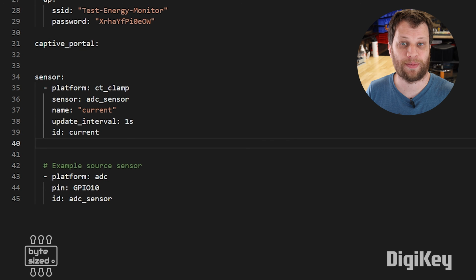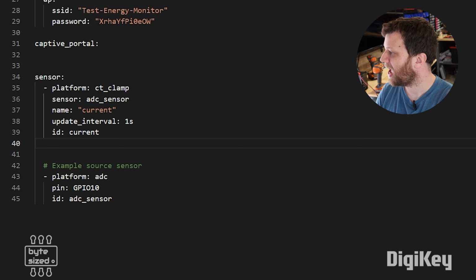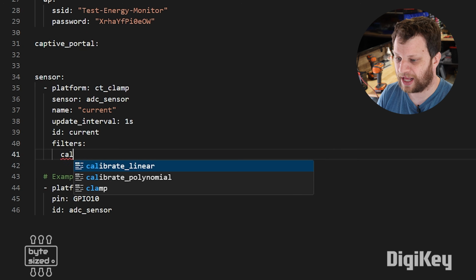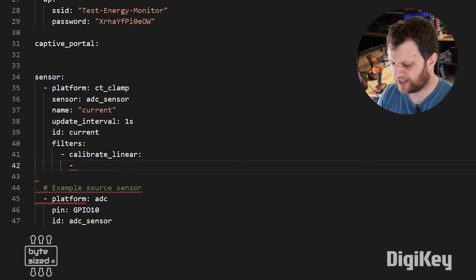This next part is really important. I need to calibrate all of the ADC readings and map them to the appropriate number of amps. So to do that, I'm going to add a filter, and I'm going to use Calibrate Linear. The syntax here is I want to map a raw ADC value of 0 to 0 amps.